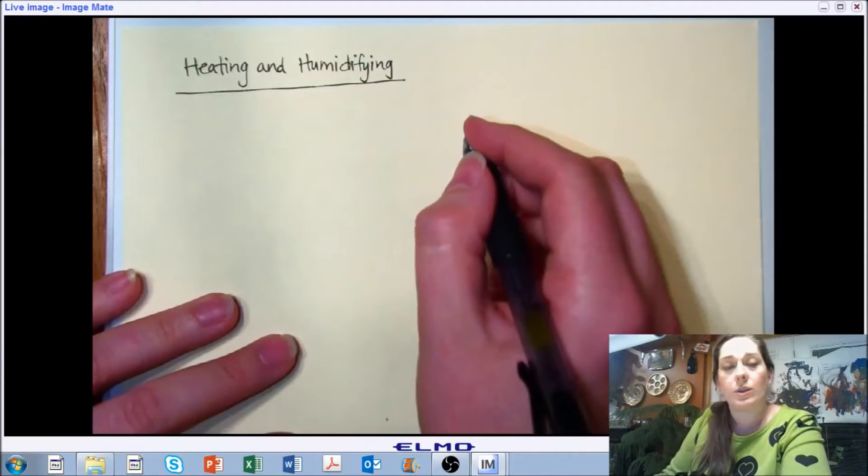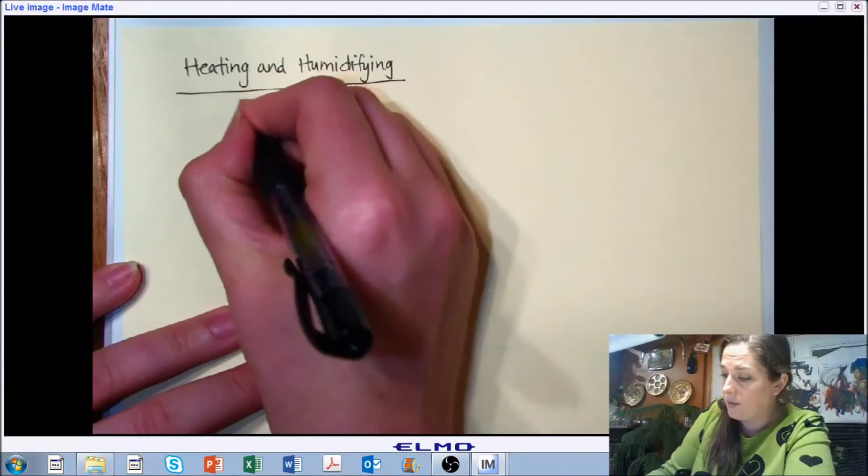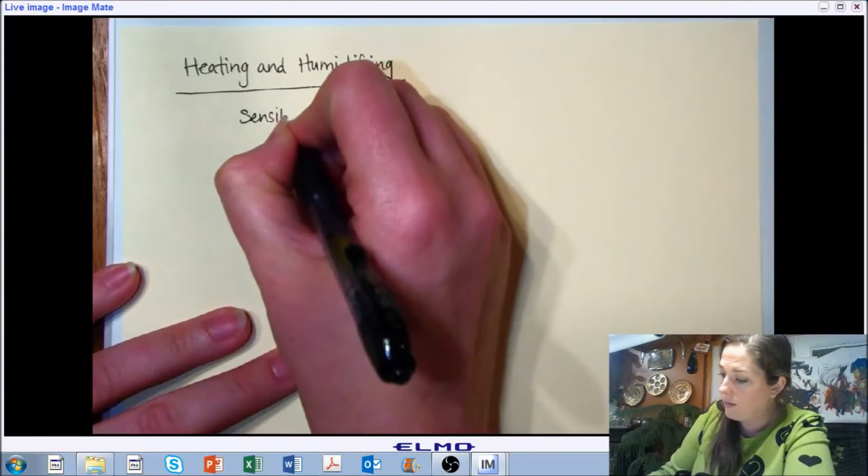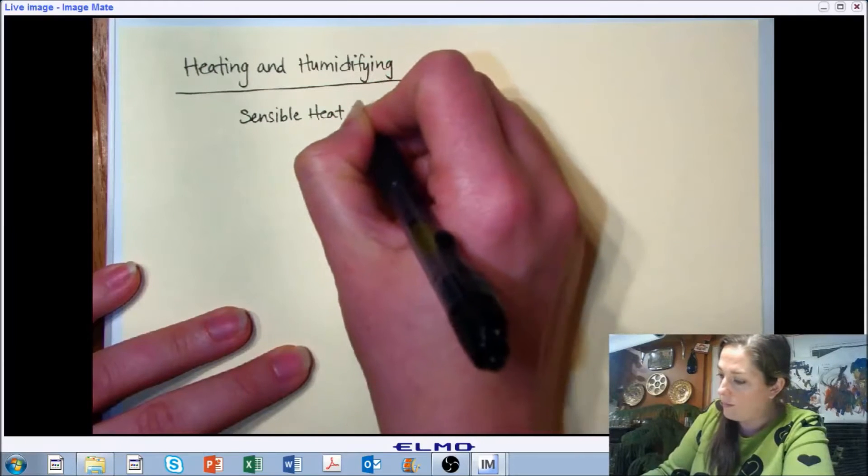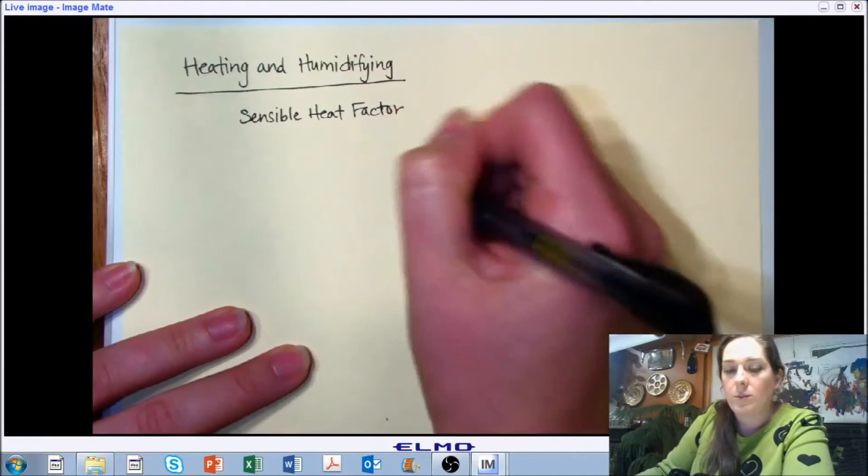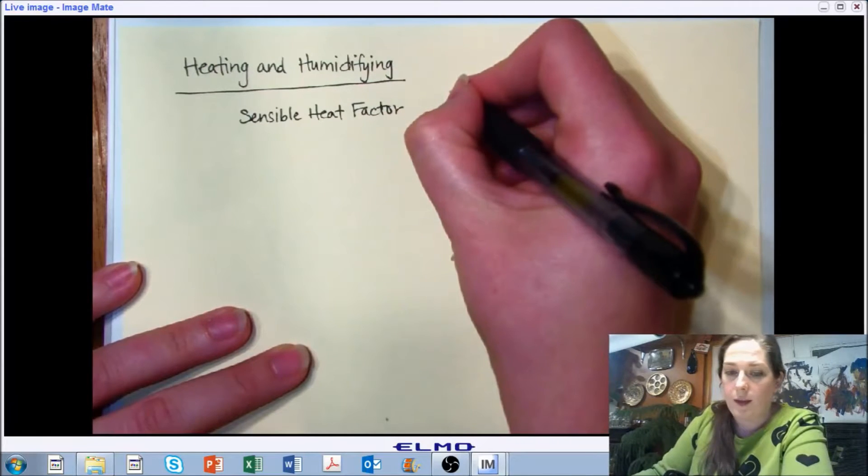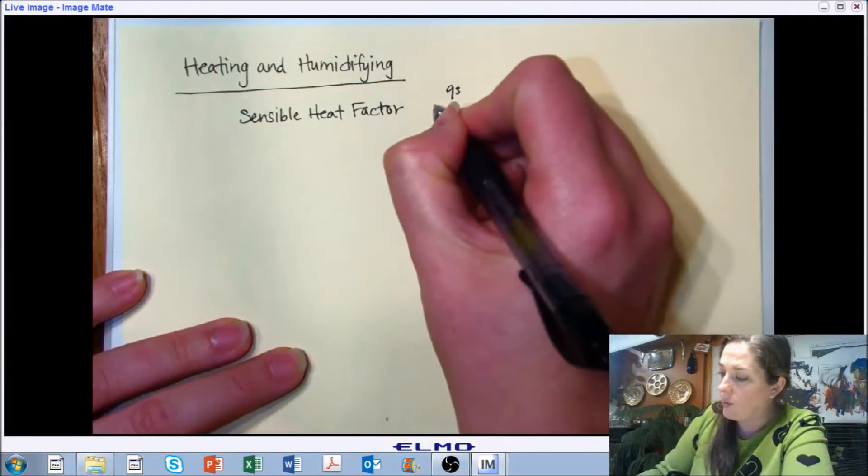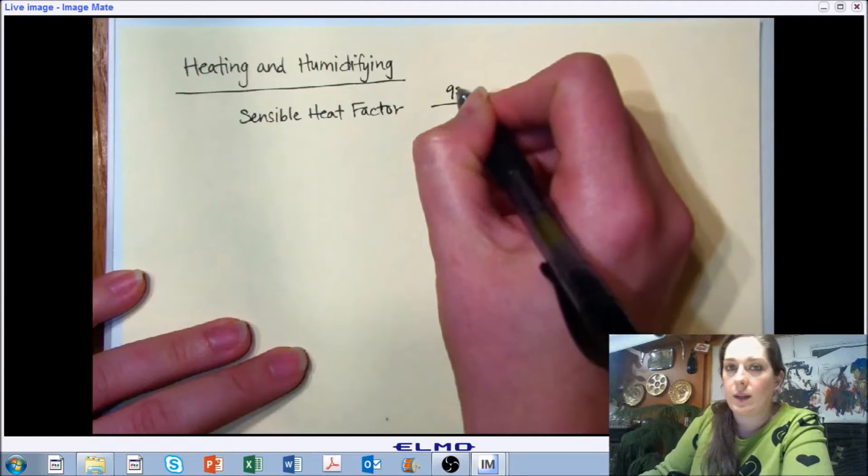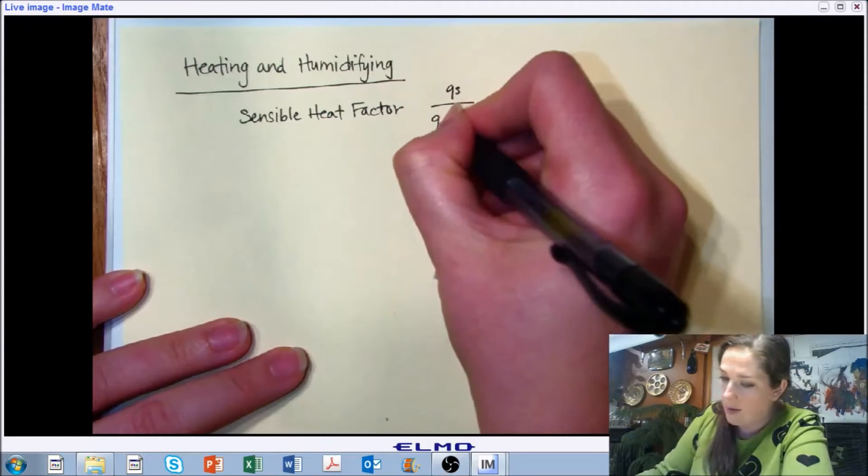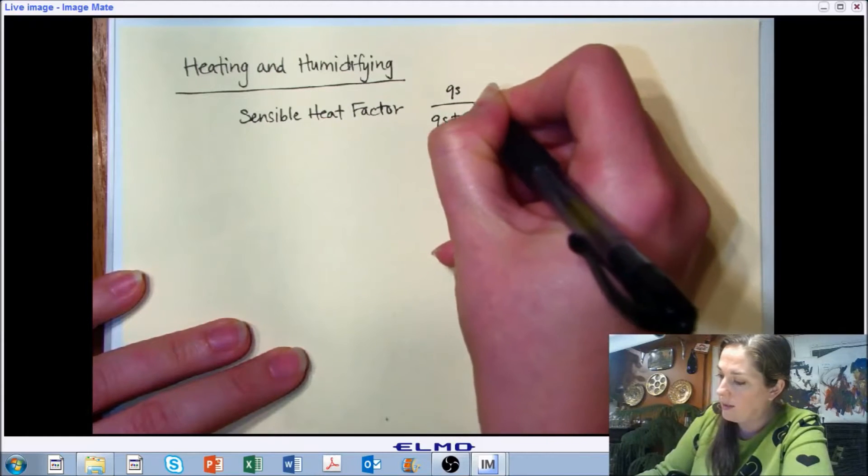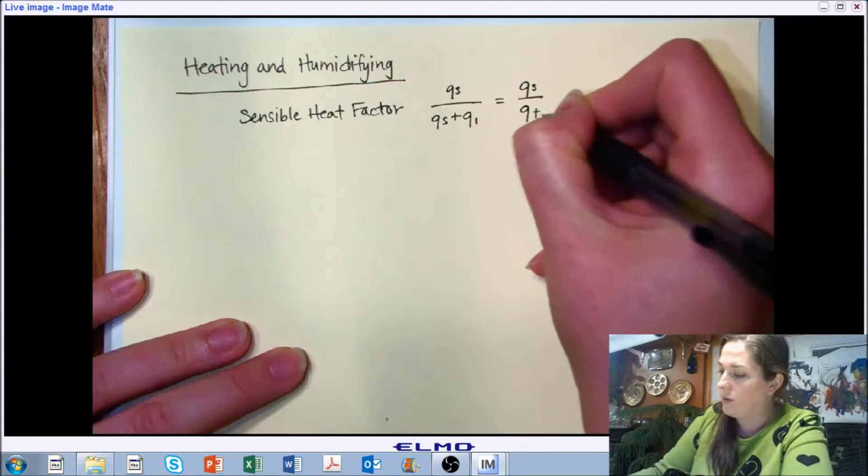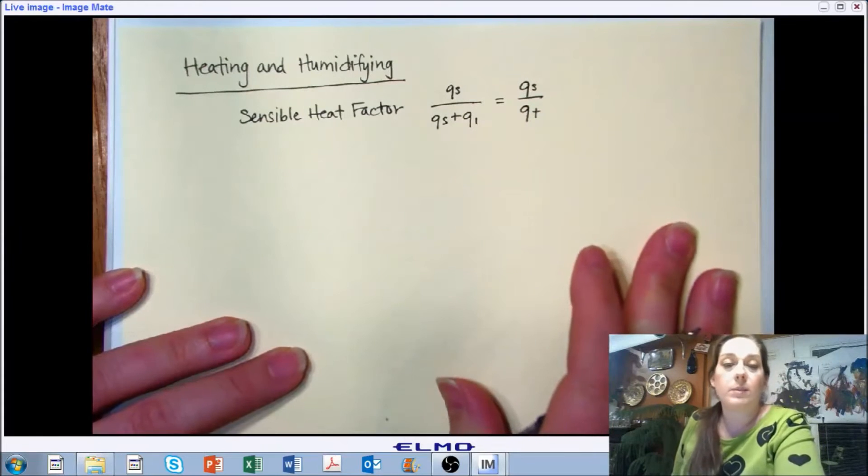Before we do too much with this, I want to introduce a new term. It is called sensible heat factor, and we're going to talk about this inside of heating and humidifying. Sensible heat factor is the relationship between your sensible and your latent and your total energy. So, the ratio between sensible and the sum of your sensible and latent, which is the same as the total energy. Qt is for total.